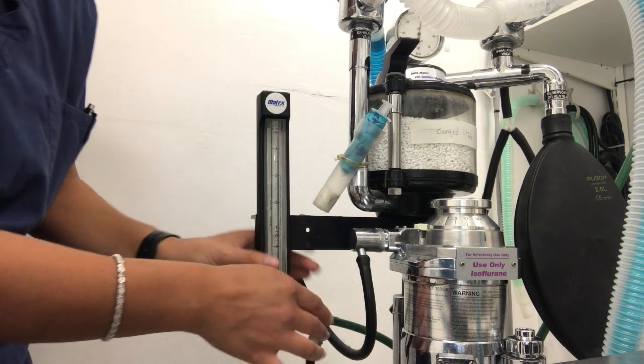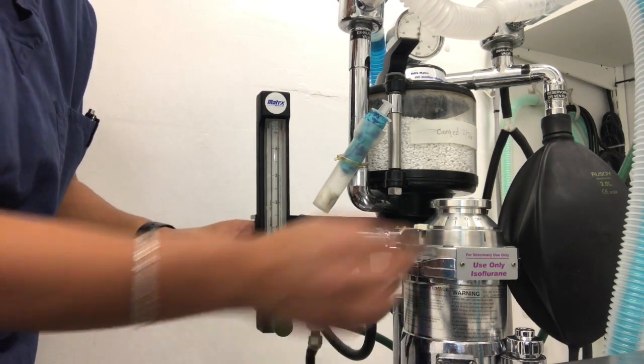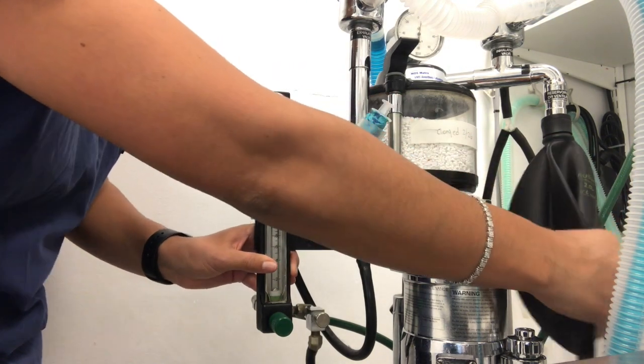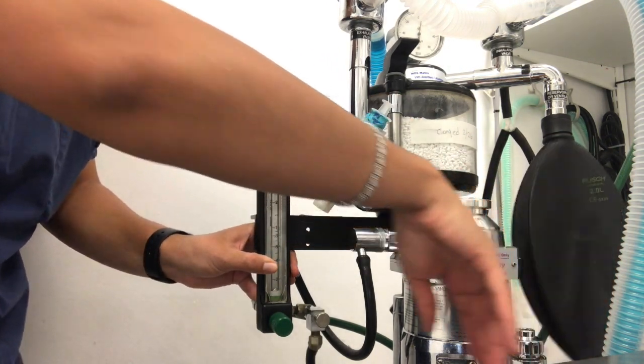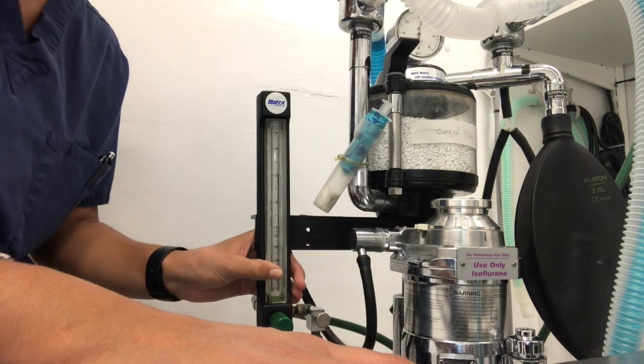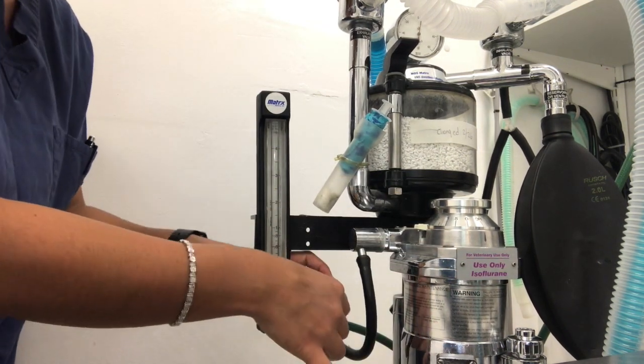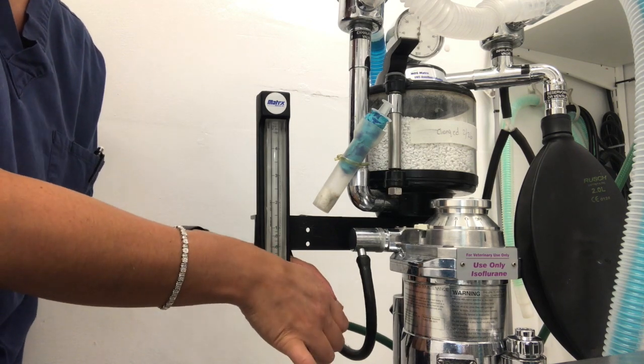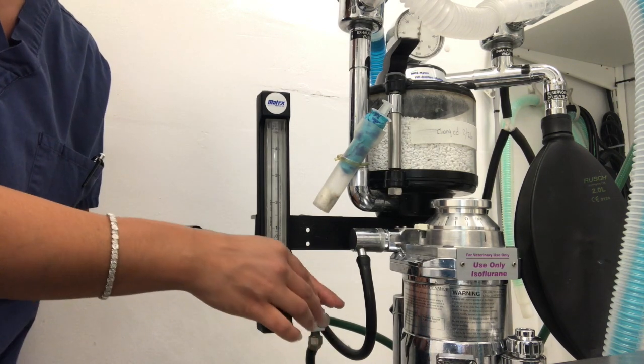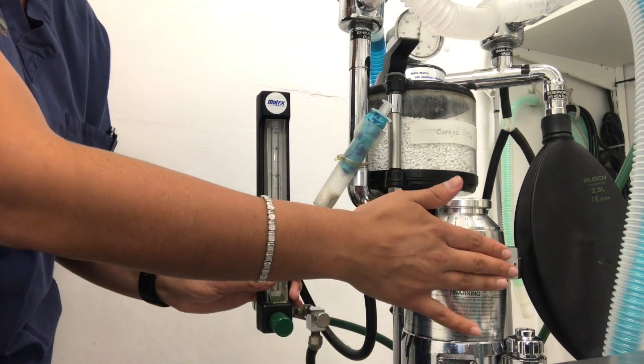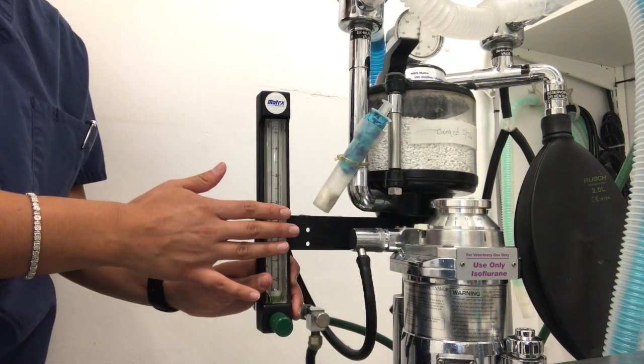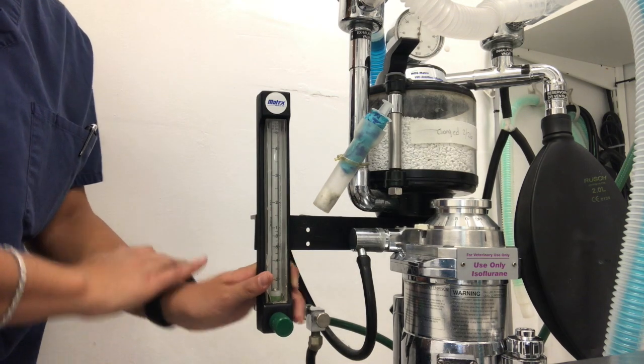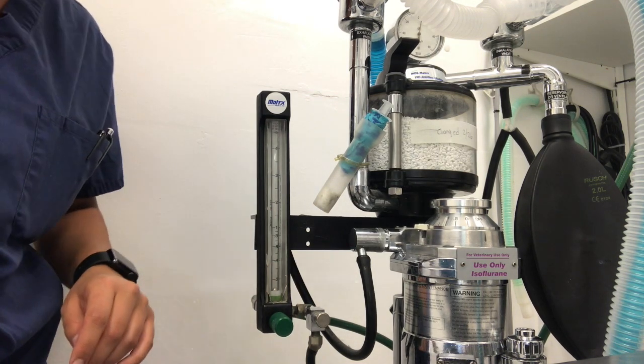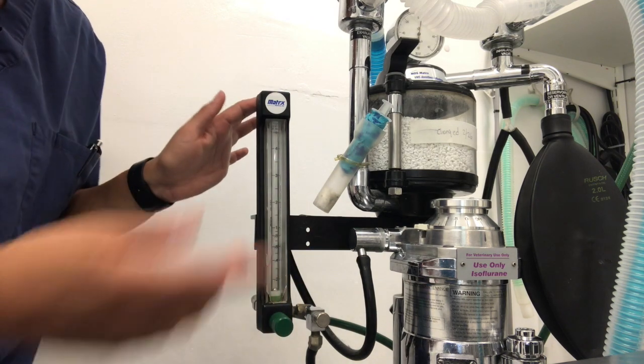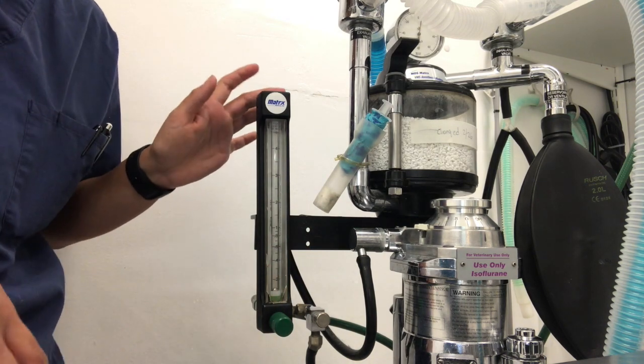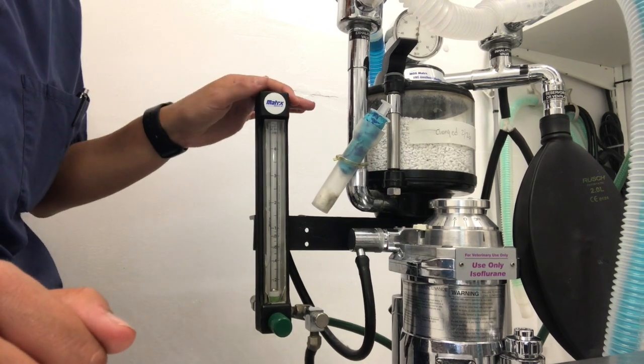Next, we have our oxygen flush valve, which is right here. As you can see, it just filled up my reservoir bag. So the oxygen flush valve is a button, and it will actually rapidly deliver oxygen in large volumes to a patient. Because of this, you actually have to be very, very careful with it, because it does bypass the anesthetic vaporizer, which is right here, and it also bypasses our oxygen flow meter. So it will allow us to rapidly fill up the reservoir bag. Reasons that we would do this is for a critically ill patient, so they would need oxygen immediately.